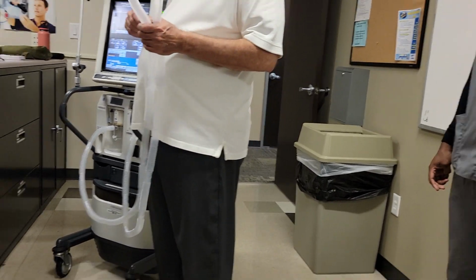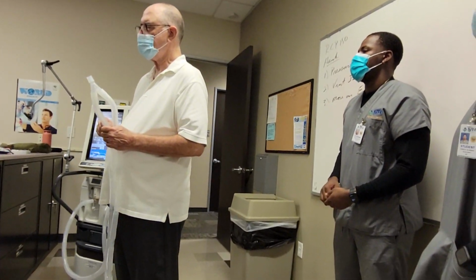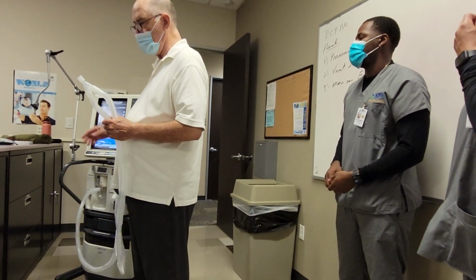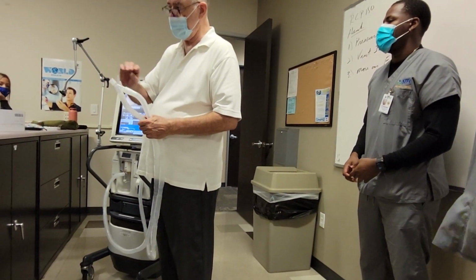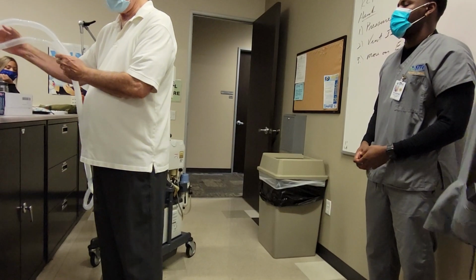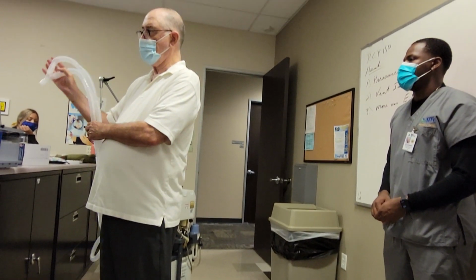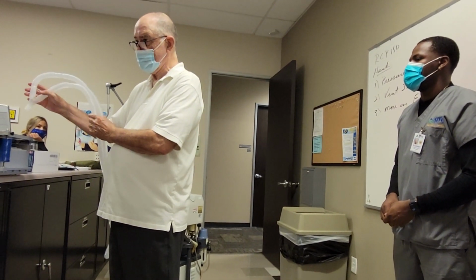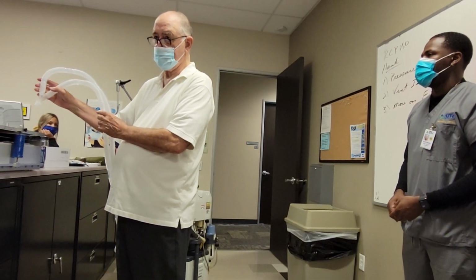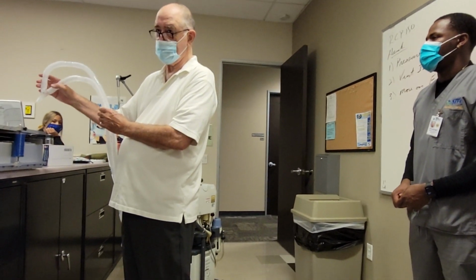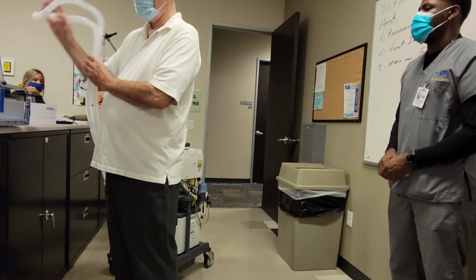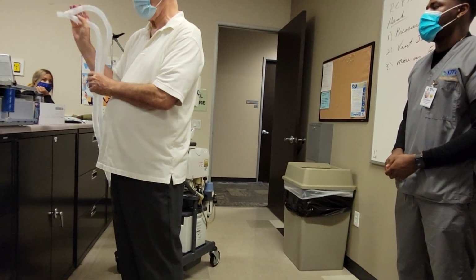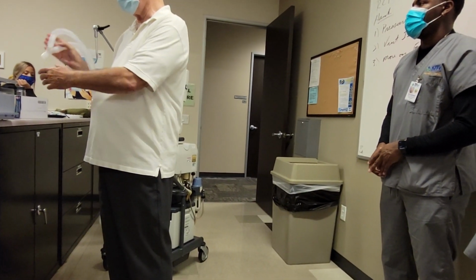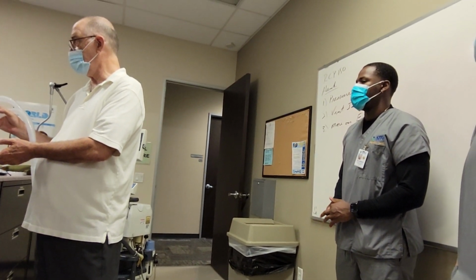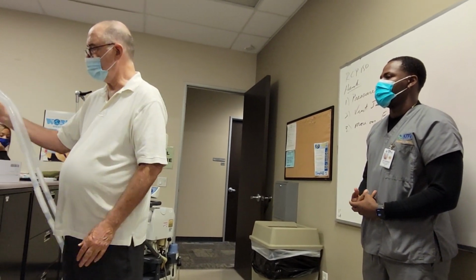If in final competency, you haven't got this all set up and you don't have gas going through here and you attach it to a patient prematurely, you will hear the fail, go to the end of the line, you lost 10%. Okay? The gas has to be coming out of there. Because if there's no gas coming out of here and you connect the patient to it, what are you doing to him? Suffocating him. Suffocating him.